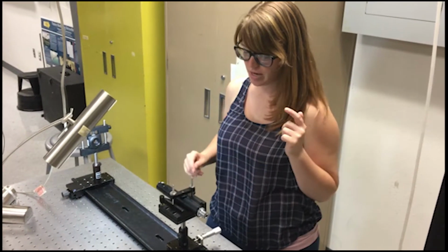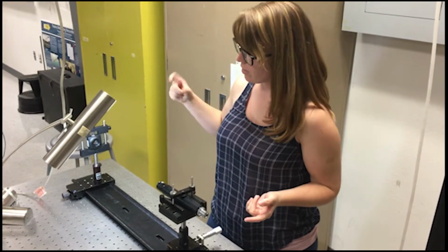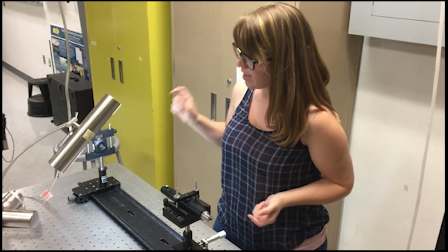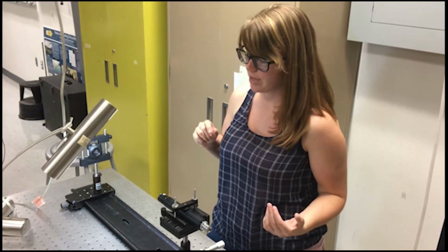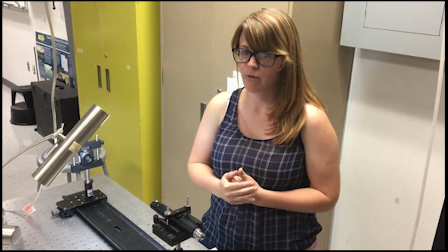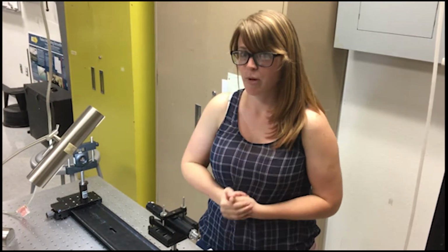This is Lab 10, Imaging System Calibration. To measure the camera's pixel size, we used a microscope on a micrometer translation stage to take horizontal and vertical measurements of the sensor, and then we looked up how many pixels there were per dimension so that we could calculate the size of each pixel. So we got 5.31 microns for each pixel size, and the datasheet for the camera says 5.3.